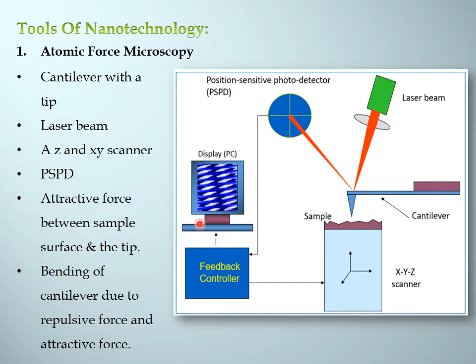Also there is a laser beam which is directed towards the cantilever, and from the cantilever the beam is directed towards the position sensitive photodetector. So that is nothing but the PSPD. Whenever the cantilever bends, the laser beam also bends, and it changes the position on the photodetector. So this will be recorded in the feedback controller, which will be sent to the monitor, where it will be displayed in the form of an image.